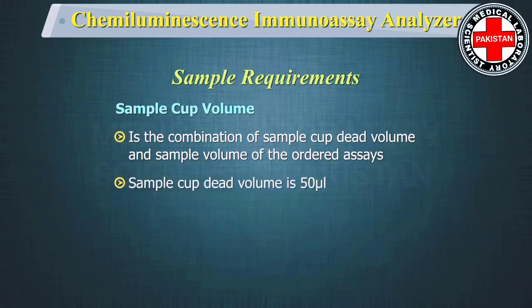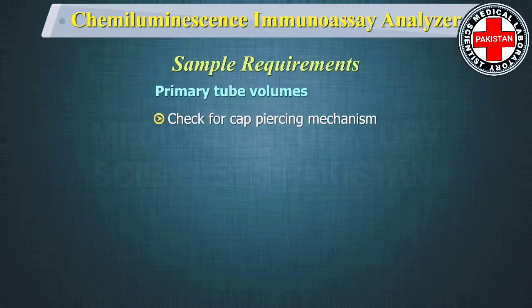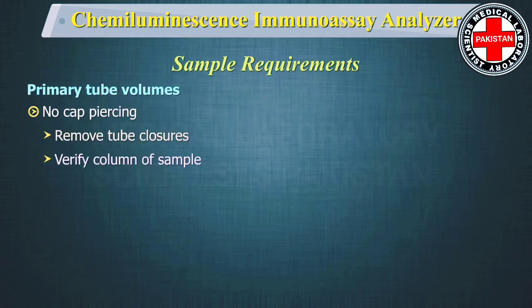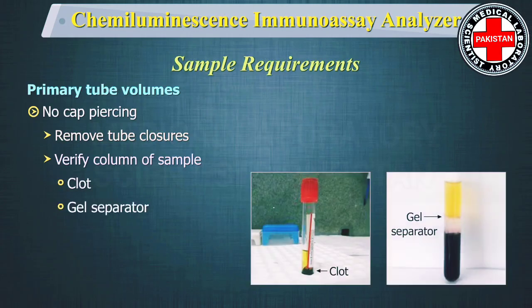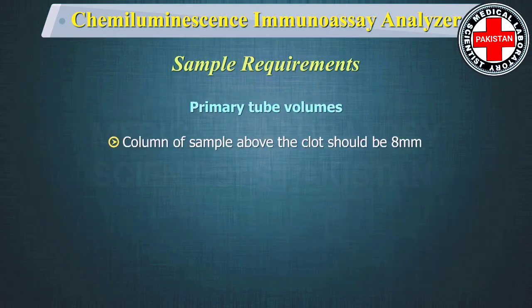For this machine, the sample cup dead volume is 50 µL. When using primary tubes, determine if your equipment has a cap-piercing mechanism. If not, remove any tube closures and verify from the user manual the column of sample that should be available above the clot, gel separator, or plasma or red cell interface. For this machine, the column of sample above the clot should be 8 mm.